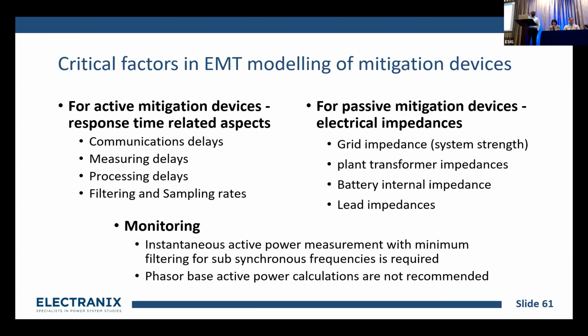Otherwise, if you try to calculate a communication delay which is not 100% right, and then play with these delays, it is dangerous, because we can create a situation which is pass or fail based on these delays. So this applies to pretty much all of these, the STATCOM and the battery with active power compensation functionality. The closed loop response time needs to be accurately modeled, or you need to check with the manufacturers how these are modeled to get the proper performance.